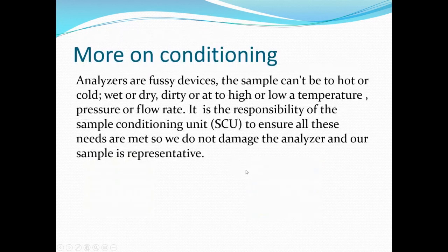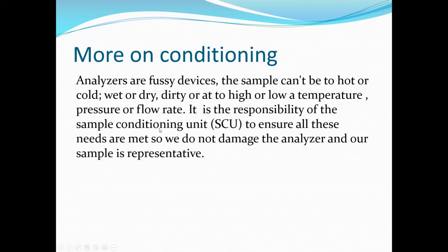In summary, analyzers are fussy — the sample can't be too hot, too cold, too wet, too dry, too dirty, or at too high a pressure or flow rate. It is the responsibility of the sample conditioning unit to ensure all these needs are met, so we don't damage the analyzer and we maintain a representative sample.